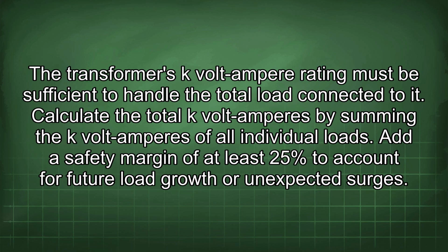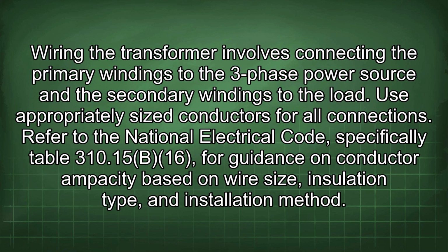The transformer's kVA rating must be sufficient to handle the total load connected to it. Calculate the total kVA by summing the kVA of all individual loads. Add a safety margin of at least 25% to account for future load growth or unexpected surges. Wiring the transformer involves connecting the primary windings to the three-phase power source and the secondary windings to the load. Use appropriately sized conductors for all connections.